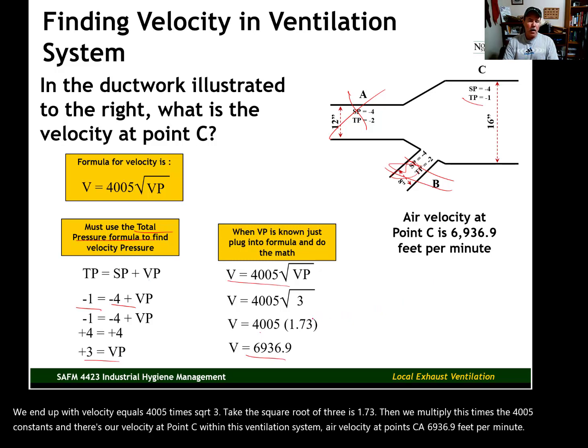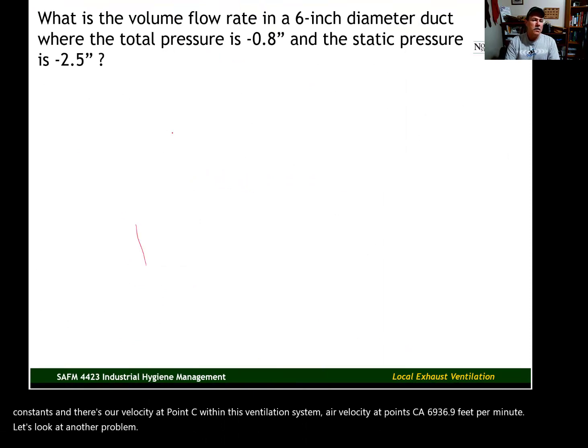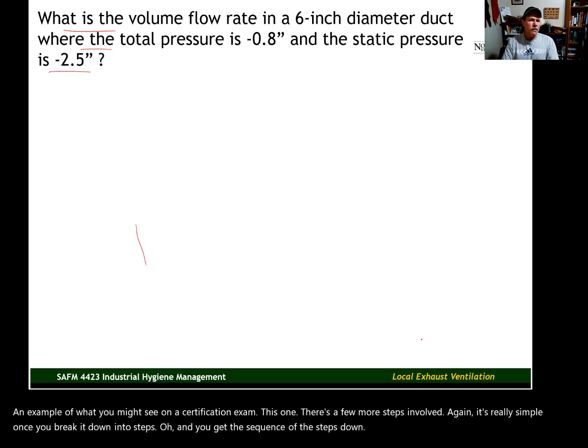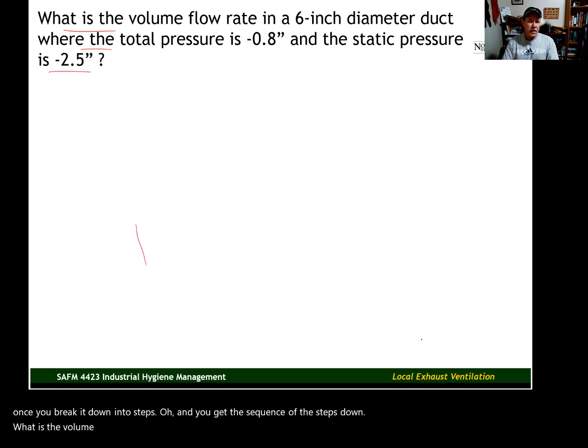Let's look at another problem. Also, an example of what you might see on a certification exam. This one, there's a few more steps involved. It's really simple once you break it down into steps, though, and you get the sequence of the steps down. What is the volume flow rate in a 6-inch diameter duct where the total pressure is negative 0.8 and the static pressure is negative 2.5 inches?